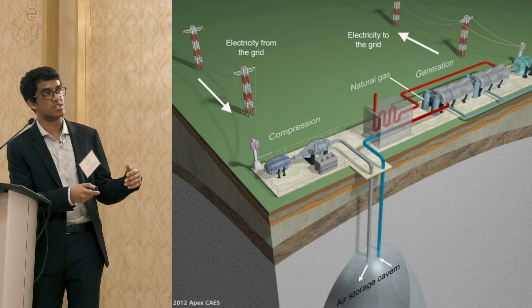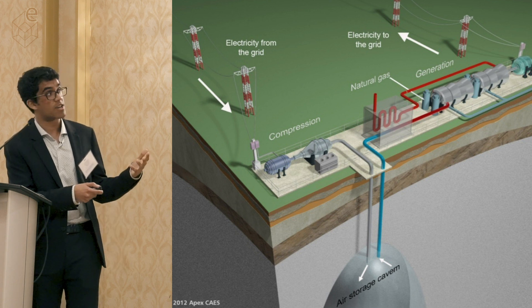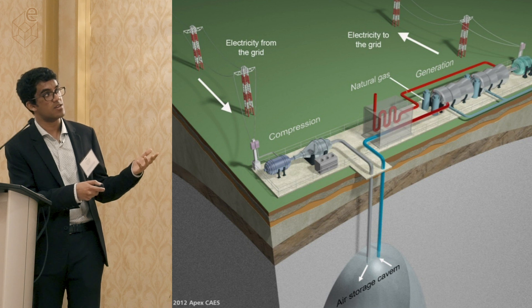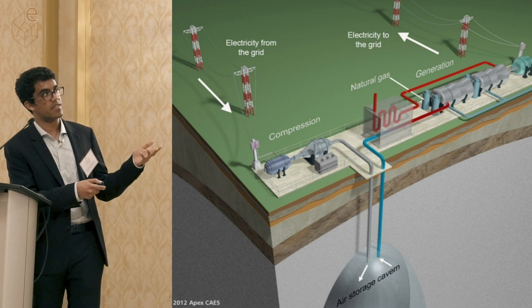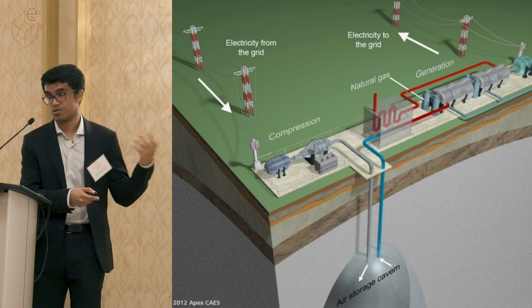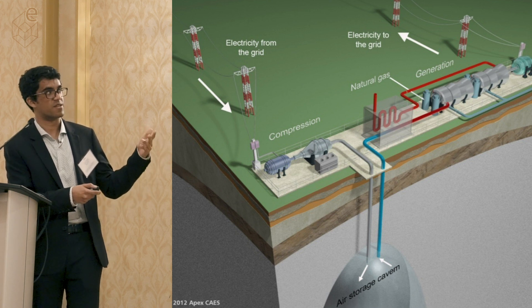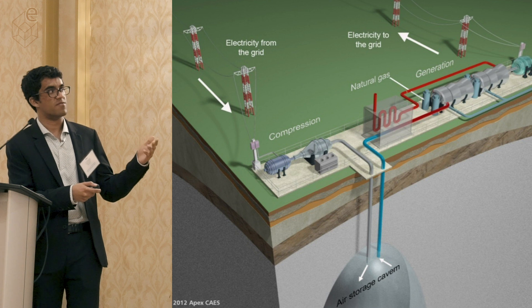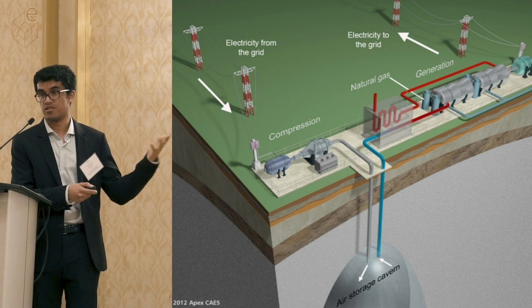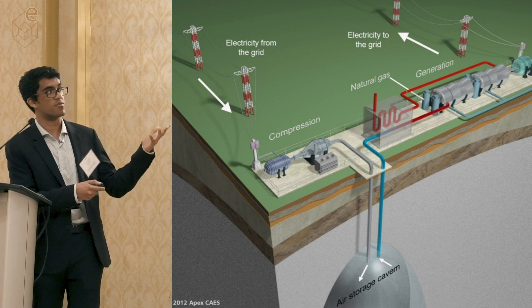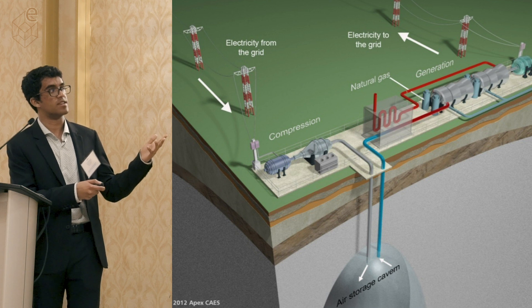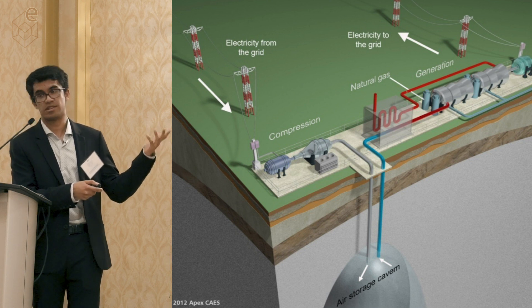This is where we make the distinction between a diabatic and an adiabatic system. A diabatic system introduces natural gas into the air to heat it up, just like a regular gas expander, producing electricity. An adiabatic alternative involves some form of heat recovery elsewhere — like a geothermal reservoir — or taking waste heat from the compressor and reintroducing it via heat exchange into the gas.